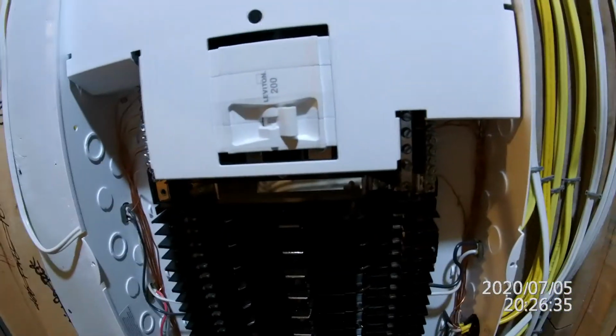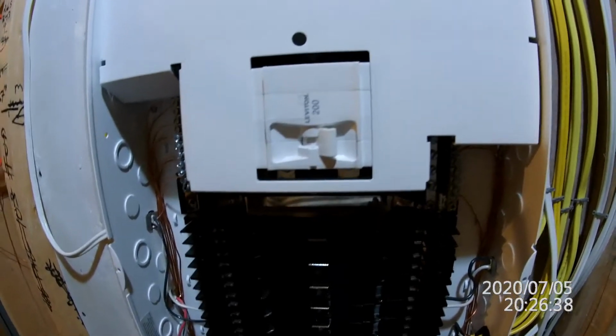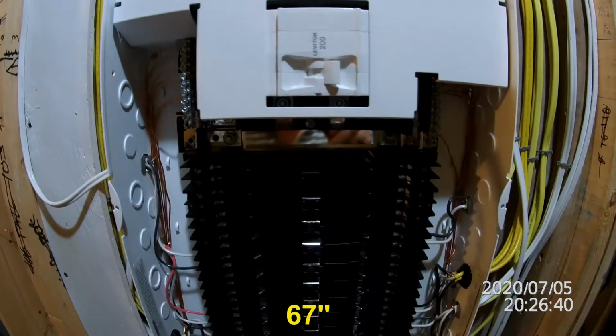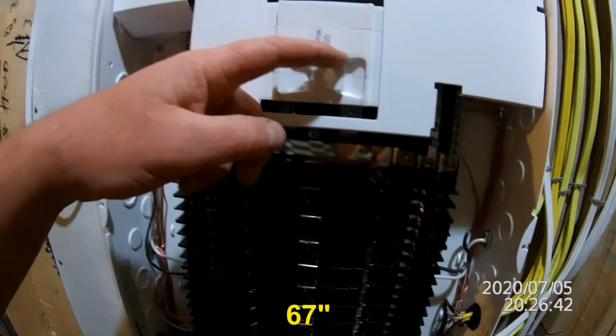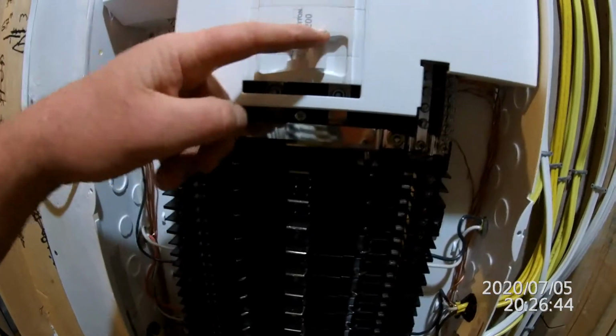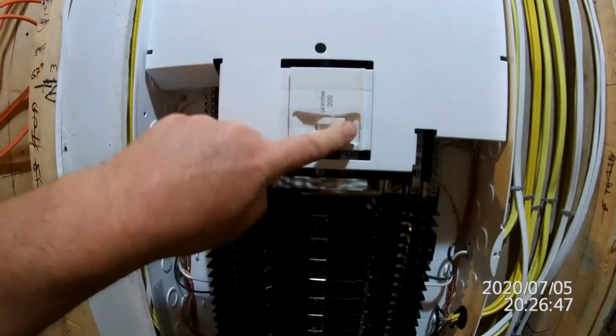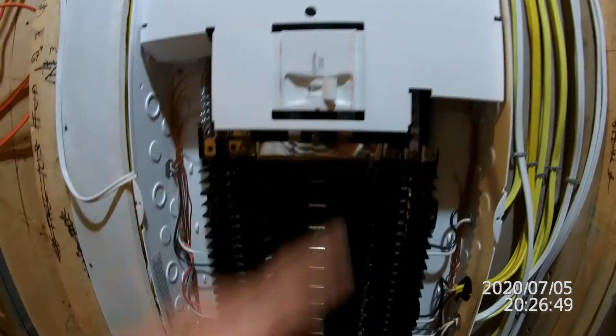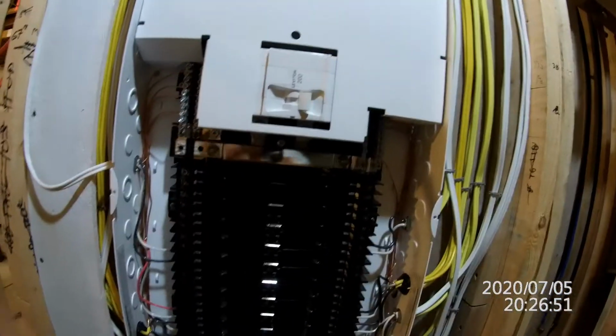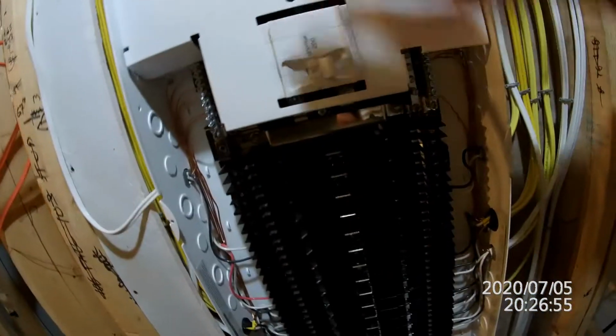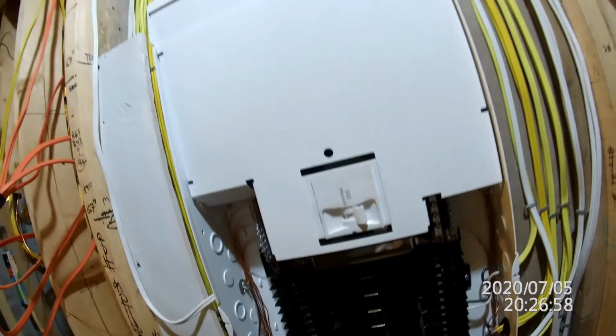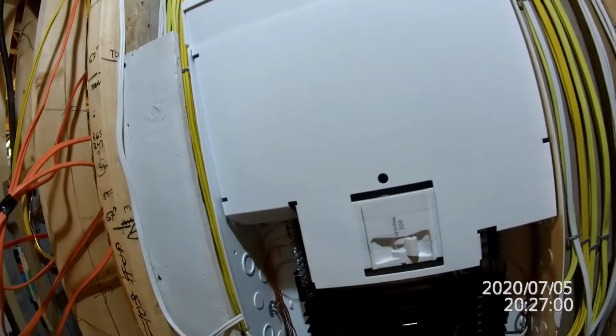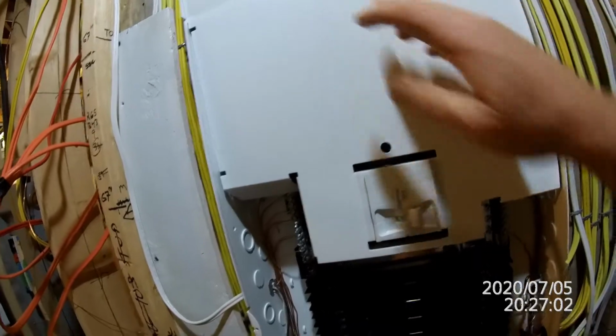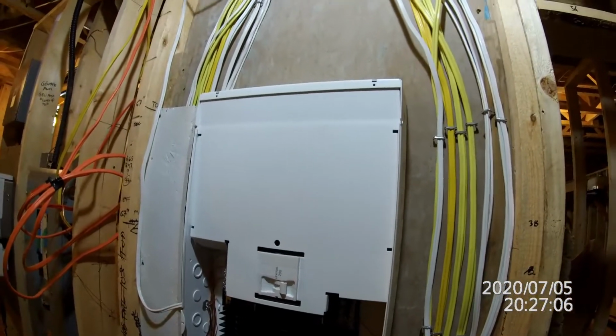I don't remember exactly what the code height is — 57 inches, 67 inches, I can't recall — but it's measured from the floor to the top of the most upper operable breaker. There's a code requirement for that. So you figure out the distance from here to here, to the top and then down to the keyhole, and you basically put a small screw in there and hang this on.